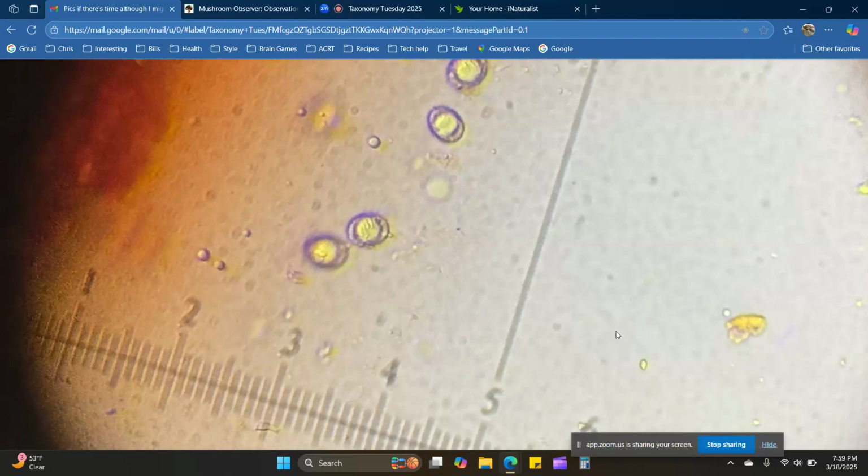Mine moves in both directions, but the setting for the 1,000 is on the left hand side, so you move that little lever all the way to the left. If you are at the lowest magnification, which is 100, then you move it all the way to the right. It could vary from model to model, but pretty much all these microscopes should have that iris lever, to adjust the amount of light coming through the condenser based on the lens setting.